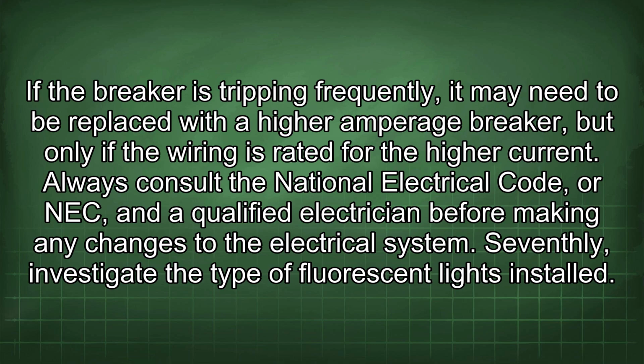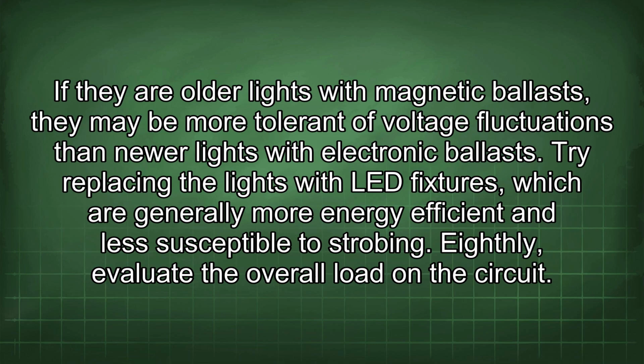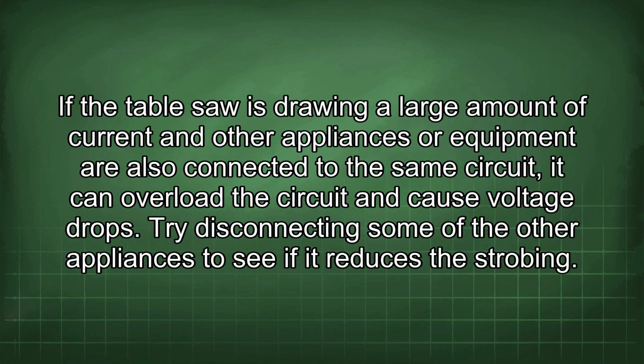Seventhly, investigate the type of fluorescent lights installed. If they are older lights with magnetic ballasts, they may be more tolerant of voltage fluctuations than newer lights with electronic ballasts. Try replacing the lights with LED fixtures, which are generally more energy efficient and less susceptible to strobing. Eighthly, evaluate the overall load on the circuit. If the table saw is drawing a large amount of current and other appliances or equipment are also connected to the same circuit, it can overload the circuit and cause voltage drops. Try disconnecting some of the other appliances to see if it reduces the strobing.